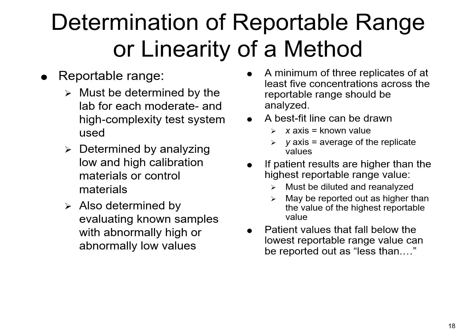Your manufacturers may tell you what the expected reportable range is, but you still have to determine it for that particular analyzer in your facility against all your environmental elements, everything. You've got to look at it all. You've got to see what it's doing in your facility. So this is done by some graphing.